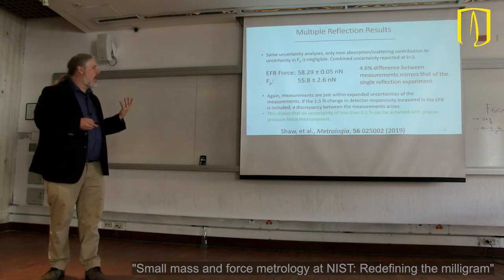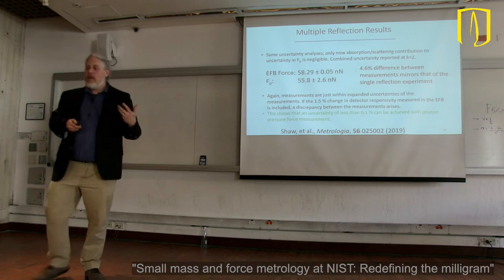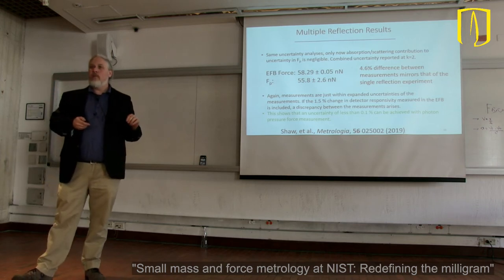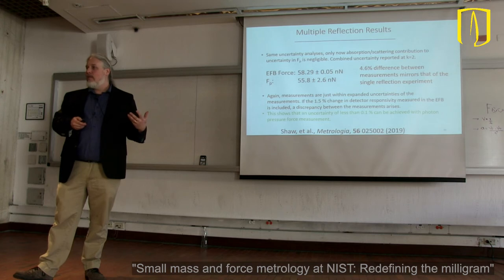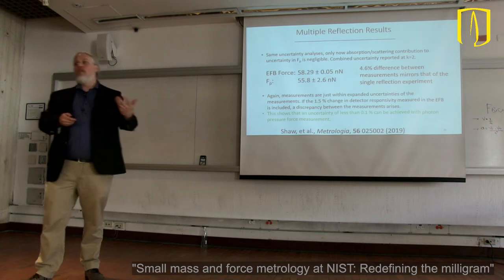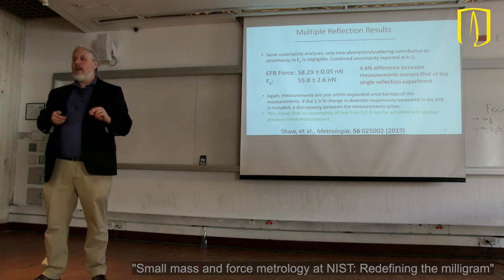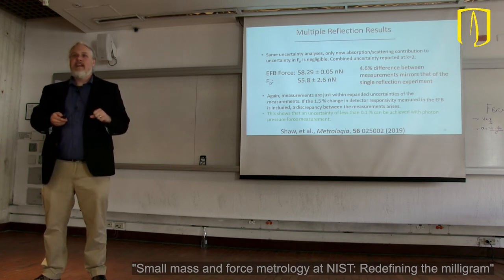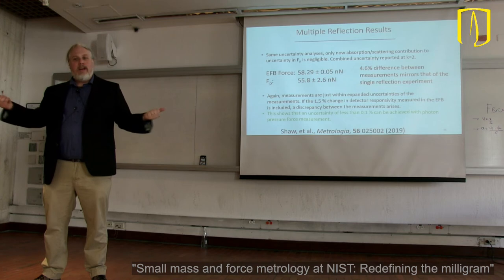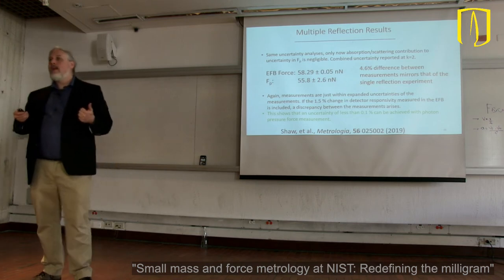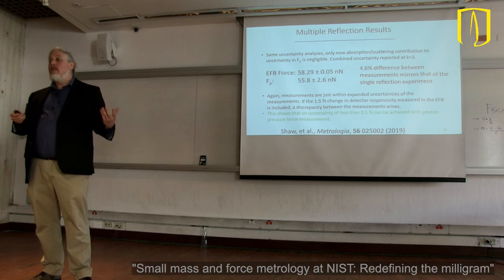Now, another thing that we see, we may have made a mistake doing these measurements. We put our detector in our vacuum chamber. The detector was calibrated in air. And it's a thermal detector, right? It is actually a thermoelectric detector. And so we can't necessarily assume that the calibration factor in air and vacuum is the same.